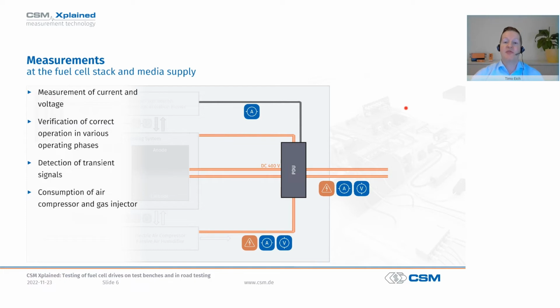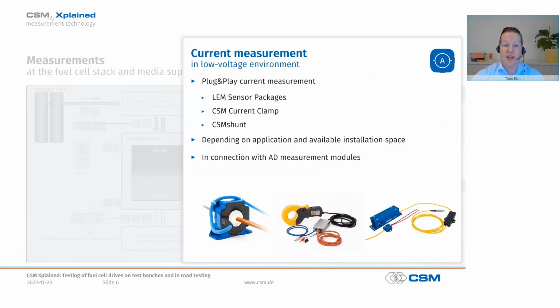For this purpose, we have to install suitable sensors, particularly for the current measurement in the various electrical paths. For the low voltage range, for example, in the anode path, we have various options here, such as ring current transformers. These are our CSM LEM sensor packages here in the picture, or we use current clamps like the CSM current clamp system, or we directly measure in the line with a current measuring resistor, a shunt, such as the CSM shunt here in the picture. And you select these depending on the application, measurement range, dynamic range requirements, and available installation space.